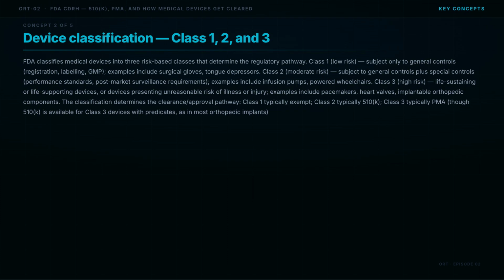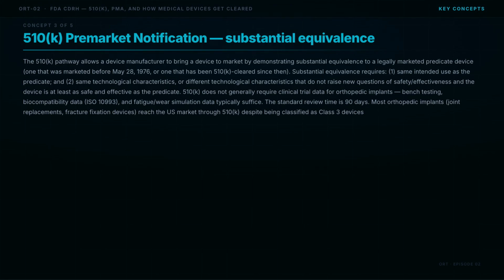Class III, high risk: life-sustaining or life-supporting devices, or devices presenting unreasonable risk of illness or injury. Examples include pacemakers, heart valves, implantable orthopedic components. The classification determines the clearance/approval pathway. Class I typically exempt. Class II typically 510K. Class III typically PMA, though 510K is available for Class III devices with predicates, as in most orthopedic implants. 510K pre-market notification, substantial equivalence.